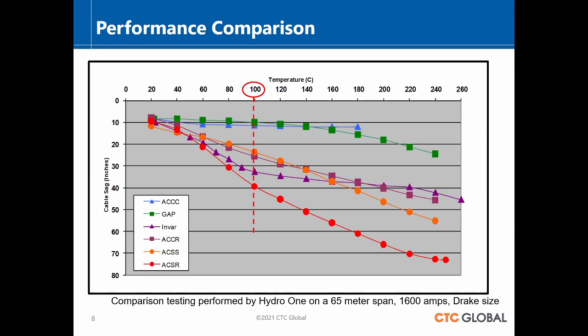Looking down at the circle where I've drawn 100, that's a little hotter than the utility actually would run an ACSR. They start annealing at a little over 90. So normally they'll operate about 75 C, 90 C, maybe 100 emergency. So I picked 100 because I got the data point there. And relatively speaking, this sag is 40 inches across 65 meters. When we're talking about a tower, of course, we're talking about many tens of meters or many tens of feet of sag that's going to be on a tower at 100 C.